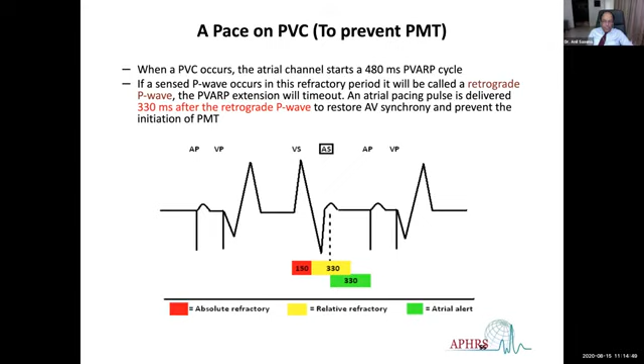And the PVC response also, in response to a PVC, despite it being retrogradely conducted, instead of giving a V pace, the pacemaker gives an A pace. So this algorithm, as soon as the pacemaker detects a ventricular premature beat, which is defined as absence of atrial activity before that, so if there is a ventricular activity without any atrial activity before that, it is counted as a PVC. And in response to that, instead of causing a V pace, it does an A pace, and that prevents induction of the tachycardia.